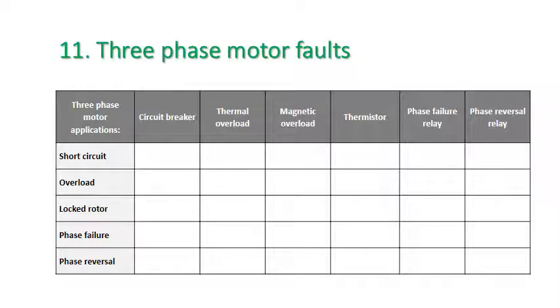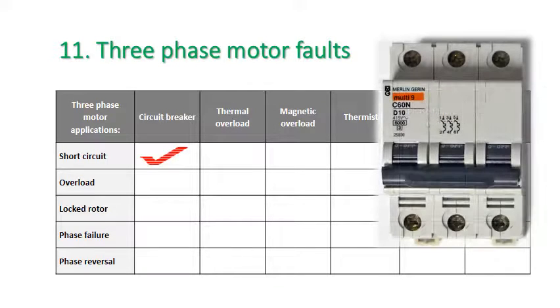I think a circuit breaker would be a pretty good choice for a start for dealing with short circuits. That's what they're good at. They have the magnetic latch mechanism in them that operates when lots of current flows. Some people might say a thermal overload or a magnetic overload might also do that. Probably they're not designed specifically for short circuits, and both of them may even be damaged if we have a short circuit. So we need some better protection upstream, and for short circuit protection I think the circuit breaker is the one to use.